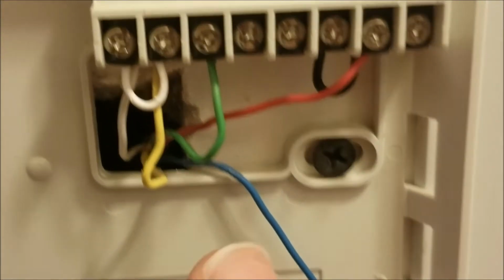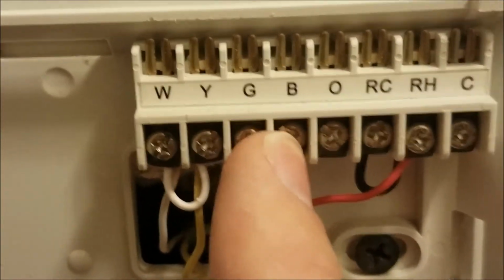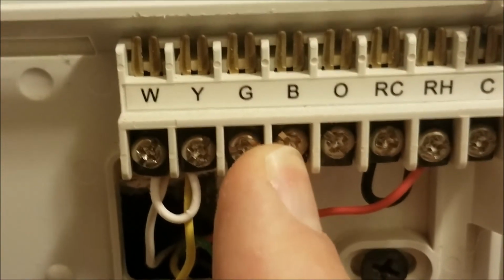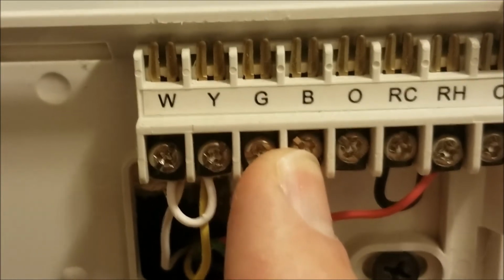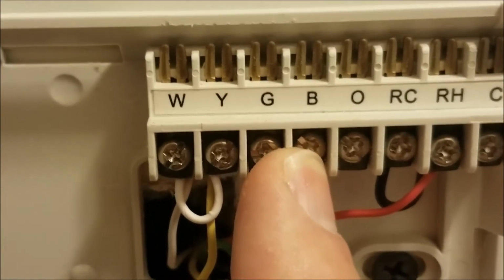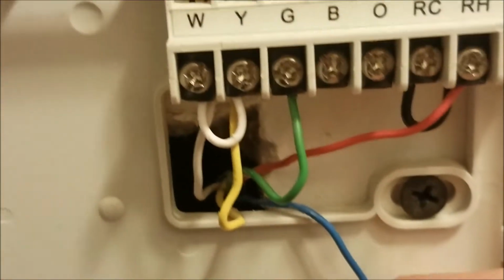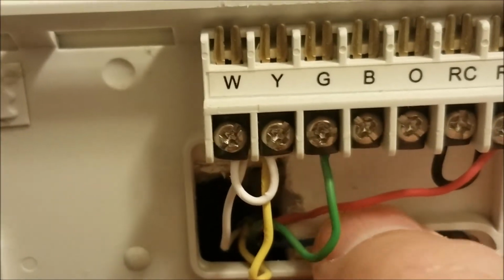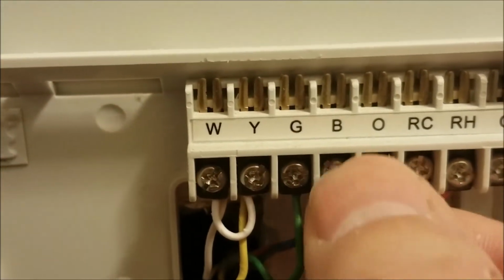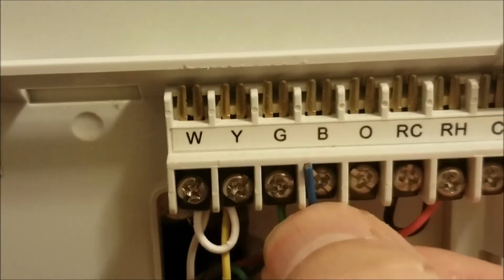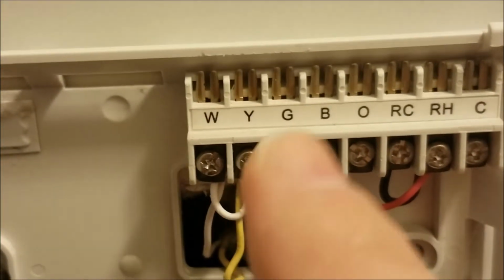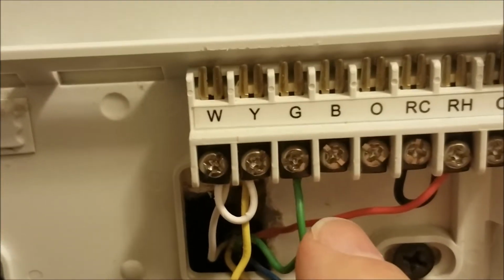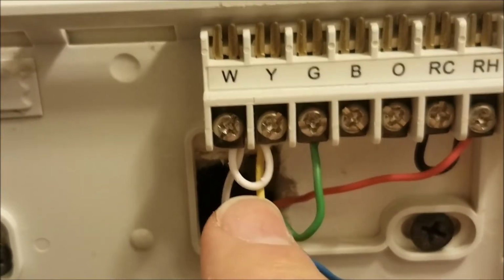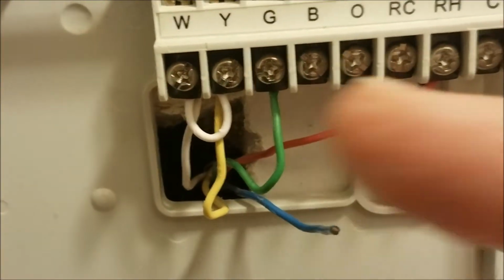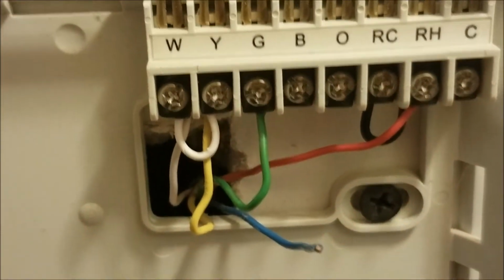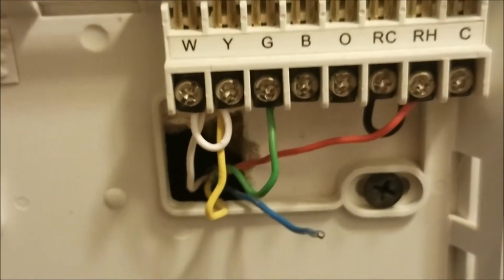Also, it has to know outside what direction the bidirectional valve, or the reversing valve, has to be in, either in heating or cooling mode. So in this case, I'm using the blue wire, and this will basically fit into here when I get it all said and done. And that will basically say, okay, you're in heating mode, and turn the compressor on, and basically this tells it which way the refrigerant needs to go in the system to provide heating or cooling. So that's kind of the basic setup.